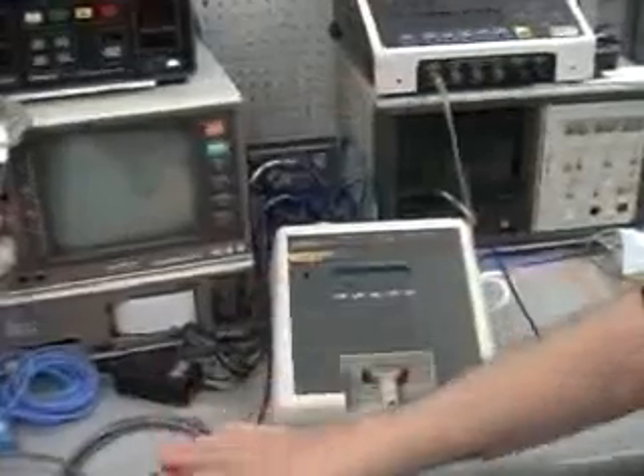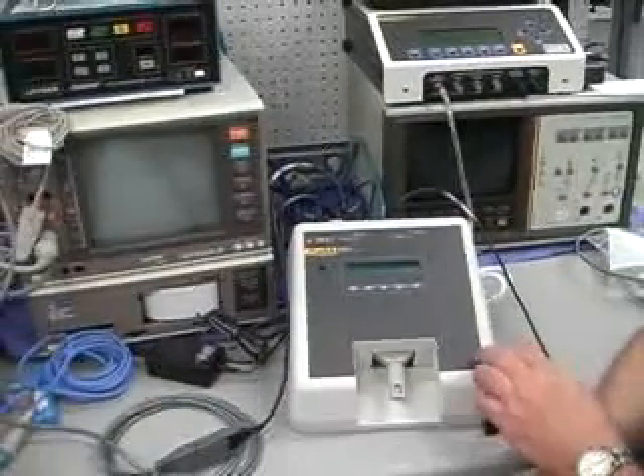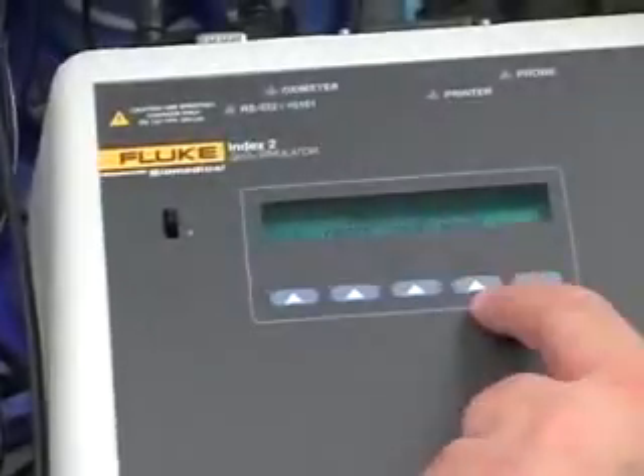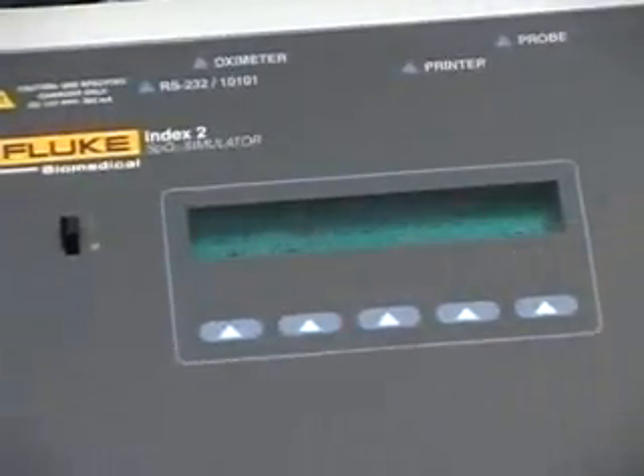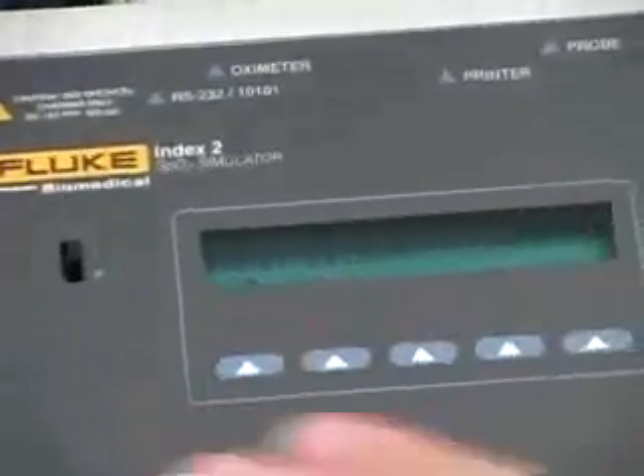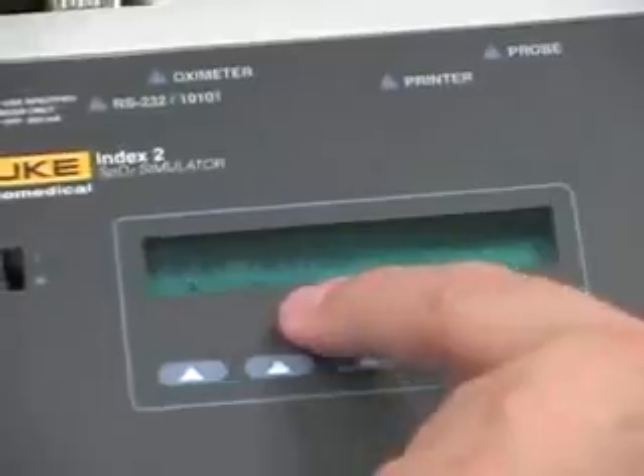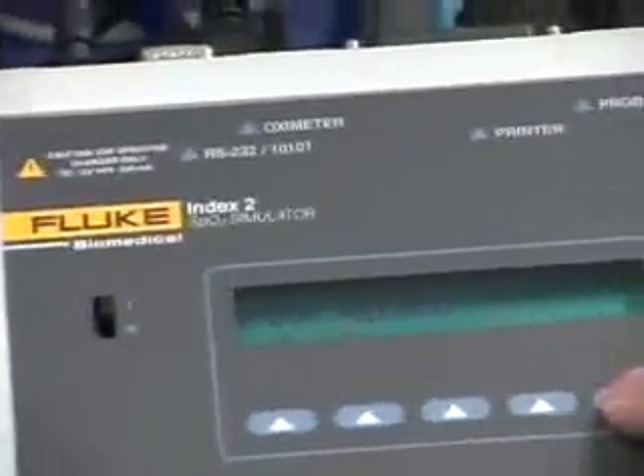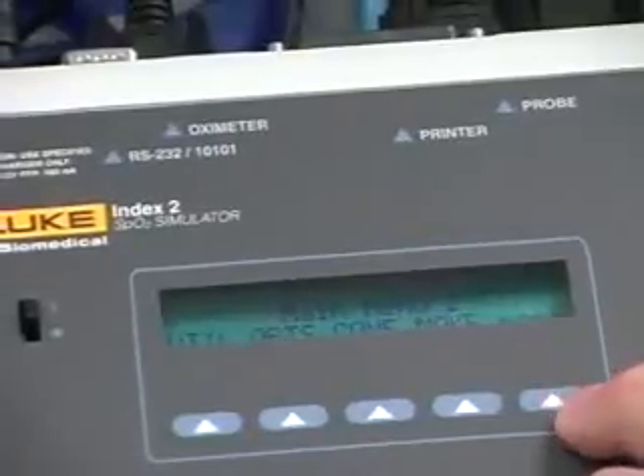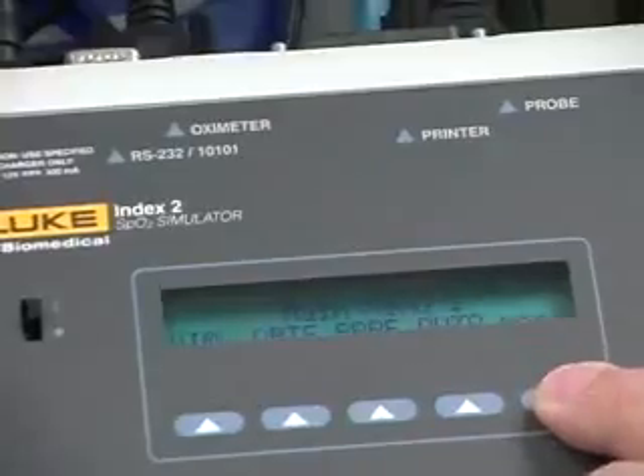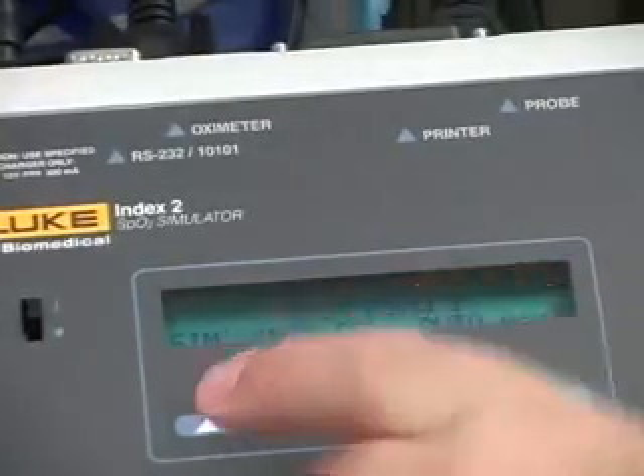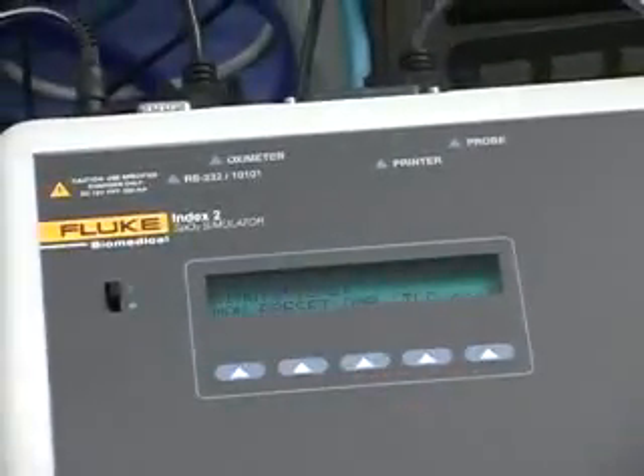Okay, so we've got the electrical output attached to the back of the index, hooked up to the Nellcor input. First, and one of the more important things, is you go into the menu, main menu number 2, F4 make, and just use the up-down keys to find Nellcor. There's no enter button, so as soon as you select it, that is active. Then just escape out of it and push F5, or the last key, until it comes up to the simulation key, and that's the F1, and now that will give you direct access to the manual simulations.